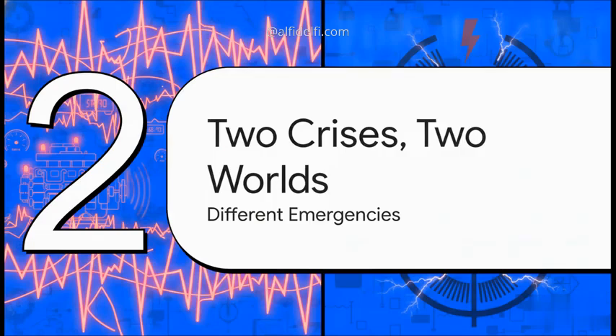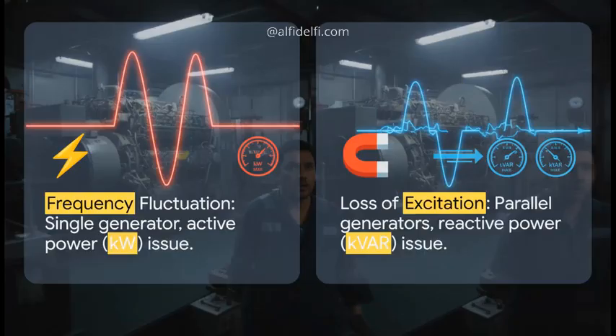Moving to Section 2. 2 crises, 2 worlds. This right here fundamentally illustrates the operational divide between these 2 emergencies. First up, let's look at frequency fluctuation. Think of this as a single generator scenario. It's a prime mover, speed control problem. Because only one generator is supplying power, an unstable frequency swinging violently between 57 and 63 Hz means your entire bus bar is unstable. It's a wild ride. This is an active power or kilowatt issue.